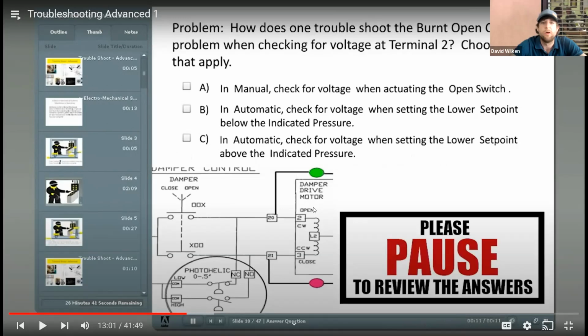All right, Nathan. We have the burnt open coil on our damper drive, and we're going to do voltage checks at terminal 2. So are we going to check in manual, for voltage when actuating the open switch? I think that's the correct answer. That's one of the correct answers, at least. So what would you expect to read on number 2 if you move the switch to the open position?